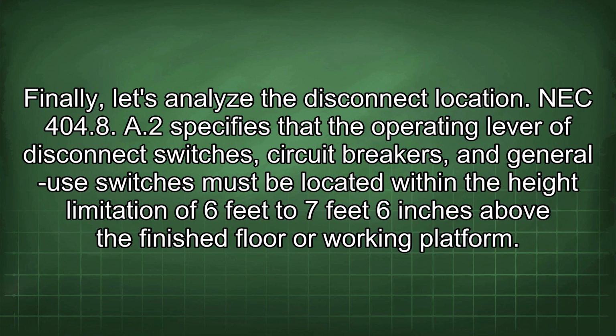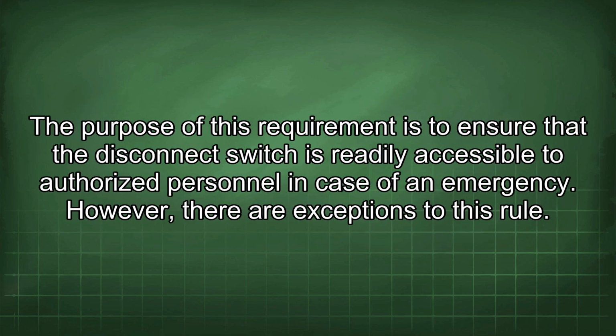NEC 404.8 A2 specifies that the operating lever of disconnect switches, circuit breakers, and general use switches must be located within the height limitation of 6 feet to 7 feet 6 inches above the finished floor or working platform. The purpose of this requirement is to ensure that the disconnect switch is readily accessible to authorized personnel in case of an emergency. However, there are exceptions to this rule.